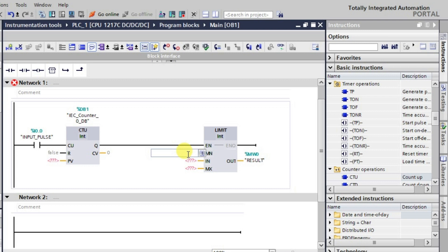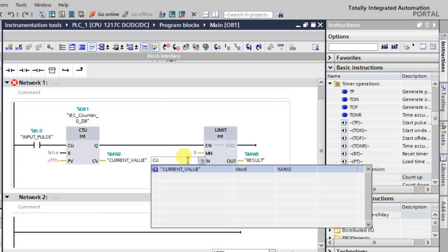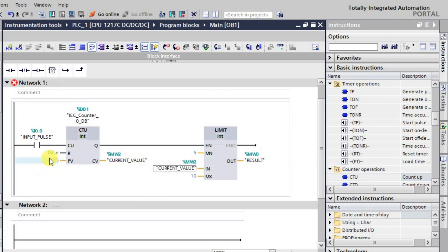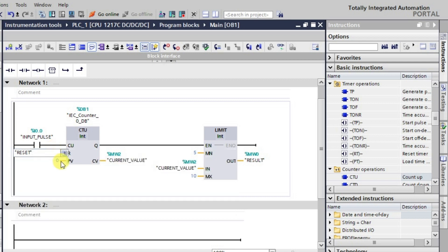The result tag will store the output of the LIMIT instruction with data type integer. The maximum value is set to 10 and the minimum value is set to 5. The current counter value feeds into the LIMIT instruction, and the reset input is also connected.